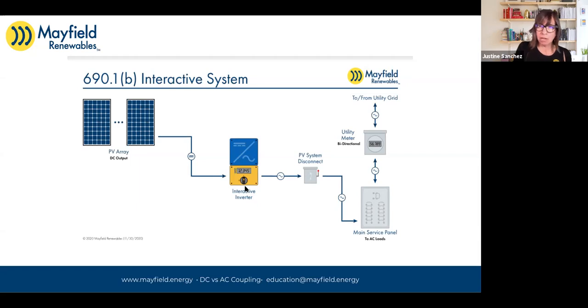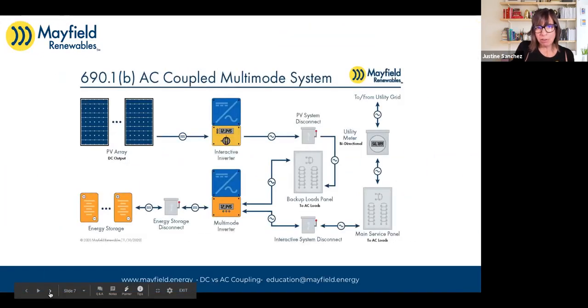But it's a financial calculation you do. Okay, it's less expensive to buy a 4 kW inverter than a 5 kW inverter. I mean, not by much anymore, but when you start getting to big systems, those calculations become more important. And so when you have an AC coupled system, you're limited by that same interactive inverter, okay? So if you have your 5 kW array here and a 4 kW inverter, you're never going to be able to get more than 4 kW off your array, even if it's producing 5.